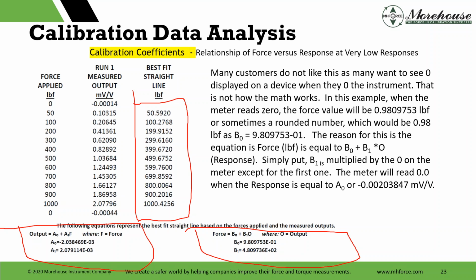And what happens here is many customers do not want to see a zero display when you use the formula. In this situation, that is just not how the math works. What they're going to do here is, if they want to solve for force, these are the coefficients: B0 plus B1, and then here on the output side, A0 plus A1. Really what I'm saying here is the force value, when the meter reads 0, if you plug these in and start doing the math and had a meter, and the meter handles the coefficients, when it reads 0, it would actually read 0.9809753 lbf, or sometimes rounded to 0.98 lbf, as the B0 coefficient is that number as we see it there.